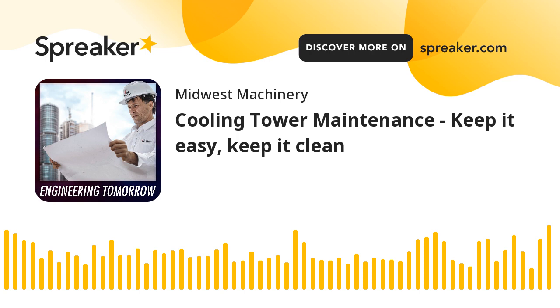So to summarize, there's not a ton of work with the tower. I don't want anyone to think that once you get a cooling tower you're constantly having to be involved with it. It's pretty maintenance-free, other than occasionally checking the things we mentioned from the hardware perspective. You get a good water program set up and it can run on autopilot, and that's really it. There's not much more to it. Like I said, you add those cottonwood screens, some sort of filter system, and good water treatment, and you're good to go. Those stainless steel towers last a long time.